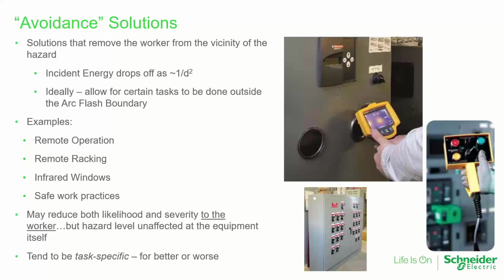One thing to notice, and again, we'll come back to this more in just a few minutes, the hazard level at the gear itself is unaffected. We may not be able to change that incident energy level that we put on the arc flash label on the equipment, or the value that you calculate in your EasyPower software, but we may functionally reduce the risk to the worker based on the tasks that they're doing. And there's one last note there at the bottom. These solutions do tend to be task specific, for better or worse. And what I mean by that, again, going back to that infrared scan, if you're the guy there with the infrared camera, that's great. It has removed the hazard for you. Doesn't do much for the next guy that comes in and has to rack the breaker back in. We'd be looking for a different type of avoidance solution in that case.